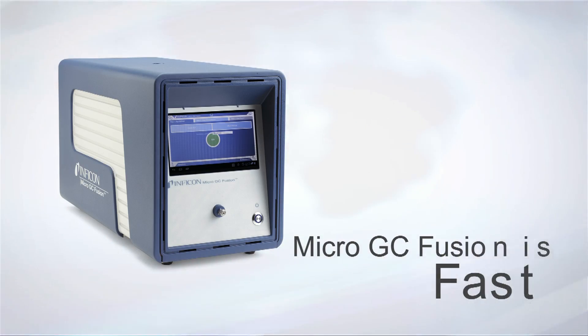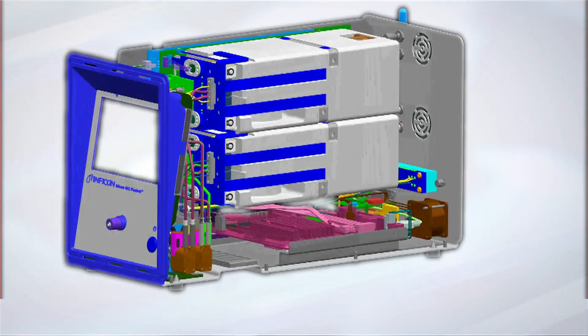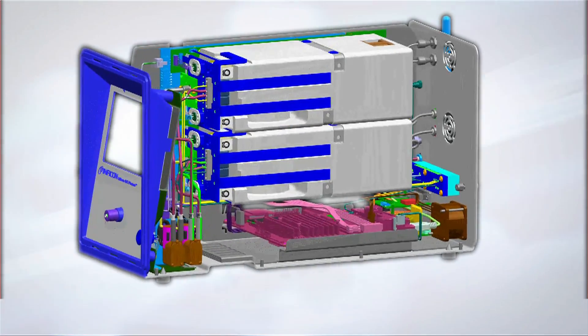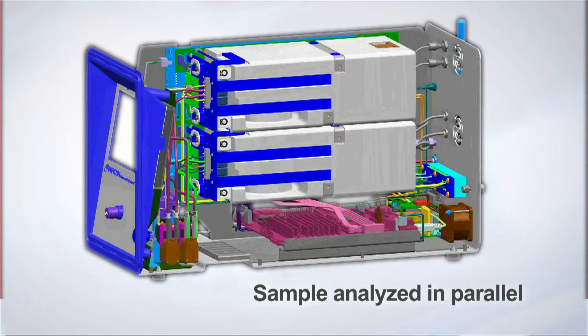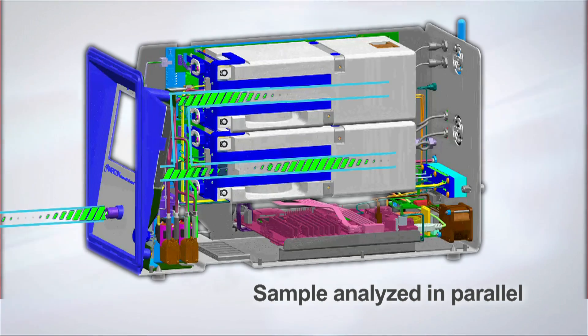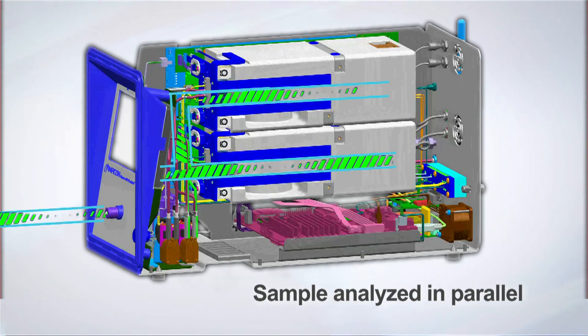Micro GC Fusion is fast. Using a modular architecture, Fusion allows the sample to be analyzed in parallel by multiple GC modules. Each module is optimized to measure at maximum speed, providing fast and accurate results.